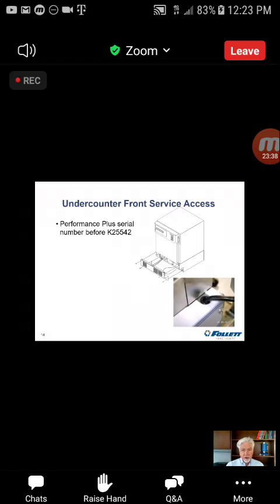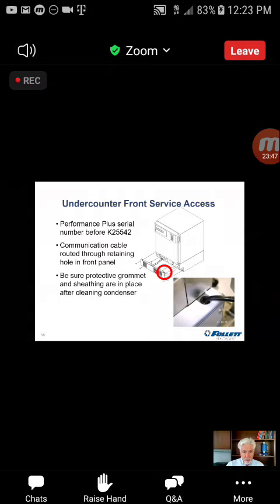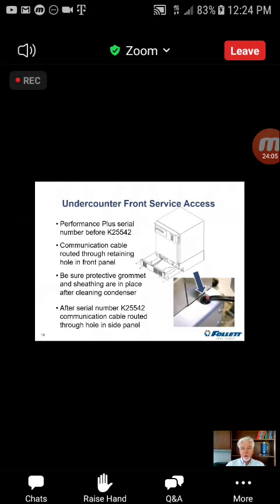So it's just a final check as you're putting the unit back together after a condenser cleaning. All right, so that hole is in the panel that you see right there. Now, after that serial number, we made a change, and that was right here. You might be able to see it. There's a relief cut around the front panel, and we changed the shape and the forming of the side panel. So that cable now goes through the side panel. It's no longer through the front panel that you see right there. So when you remove that, the cable stays in place.